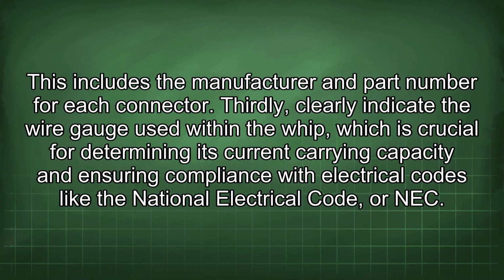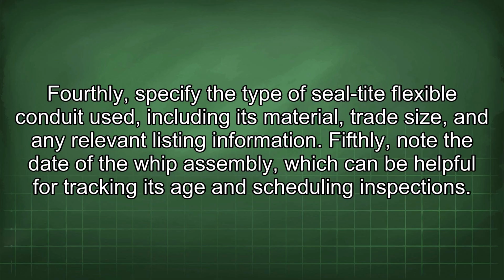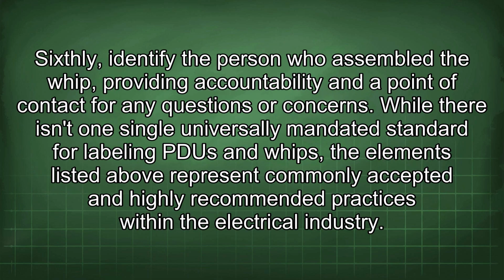Thirdly, clearly indicate the wire gauge used within the whip, which is crucial for determining its current carrying capacity and ensuring compliance with electrical codes like the National Electrical Code, or NEC. Fourthly, specify the type of Seal-Tite flexible conduit used, including its material, trade size, and any relevant listing information. Fifthly, note the date of the whip assembly, which can be helpful for tracking its age and scheduling inspections. Sixthly, identify the person who assembled the whip, providing accountability and a point of contact for any questions or concerns.